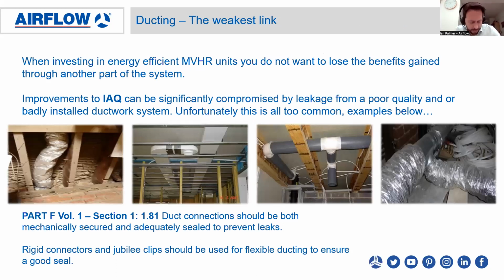So we're coming towards the end of the CPD now. Just going to briefly talk about the ducting system, because this is equally important when you're installing an MVHR system to get it right. When investing in an energy efficient MVHR unit, you do not want to lose the benefits gained through another part of the system. Improvements to indoor air quality can also be significantly compromised by leakage from a poor quality and badly installed ductwork system. And unfortunately, this is all too common. You'll see some examples below of some poor installations here.